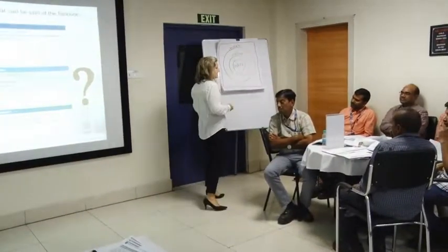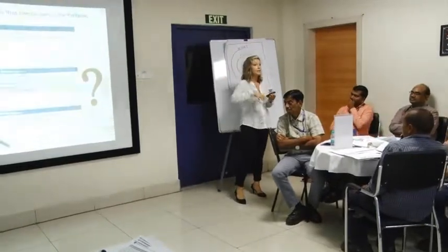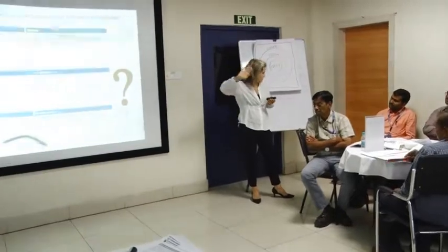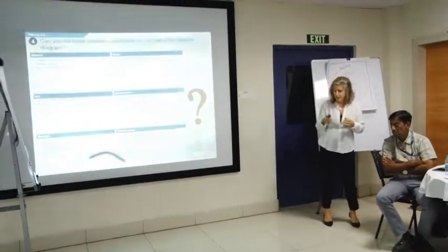Can I go a little bit out of temperature? Can I go like 2 degrees up, 2 degrees down, and it's still going to be good? That's how it can handle some variability. Okay? So how robust is your method? And did you go outside of the validated ranges? Okay? Critical control points and the adequacy of those parameters. If it's a method, did you do your system suitability? HPLC, right? Usually we run 6 or 7 and then we do a blank just to clean it, make sure. Depends on the method, right?